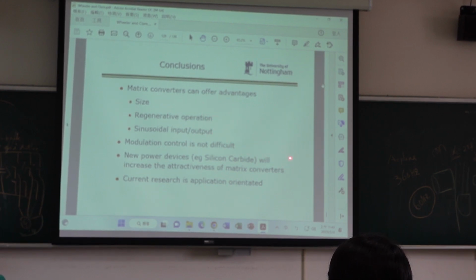Sometimes the motor can provide power back to the grid. What is the purpose? Saving energy. Before, if you needed to reduce speed, you used a resistor to waste the power. But now you can return power to the power grid, saving energy — this is regenerative operation. You also have sinusoidal input current, sinusoidal output current, unity power factor, one-stage power conversion, and high efficiency. So these are some advantages.